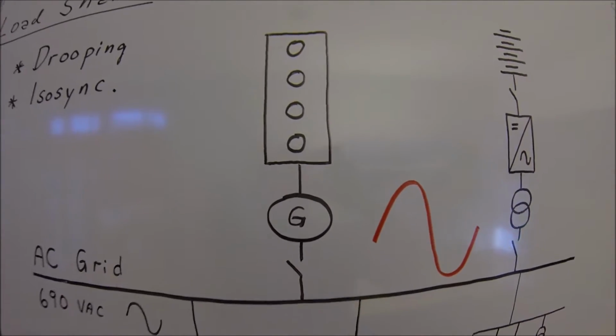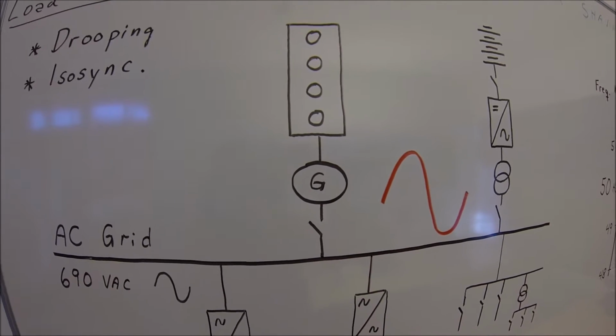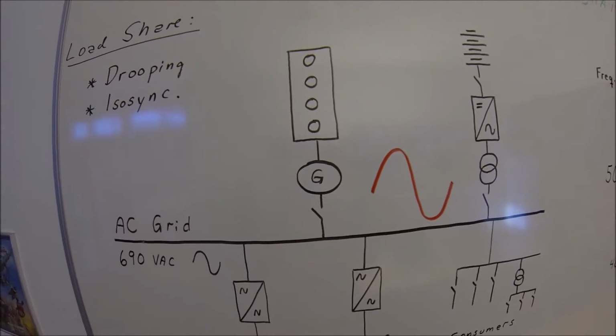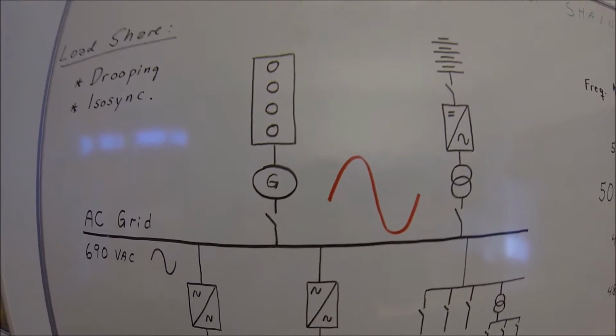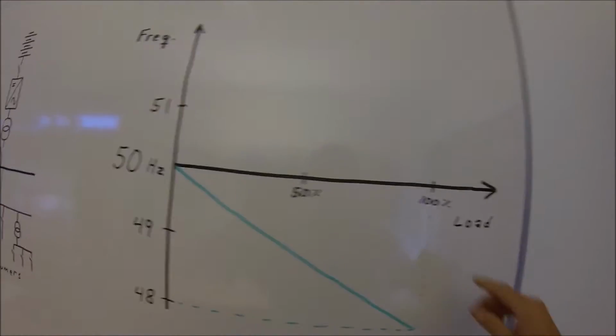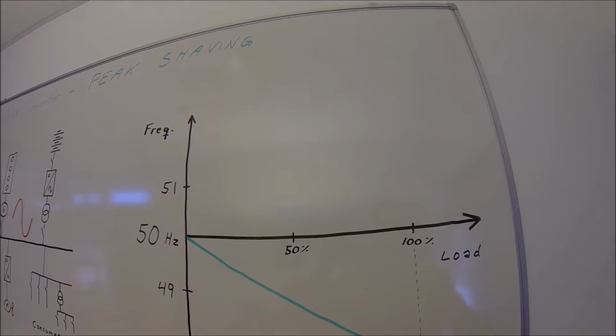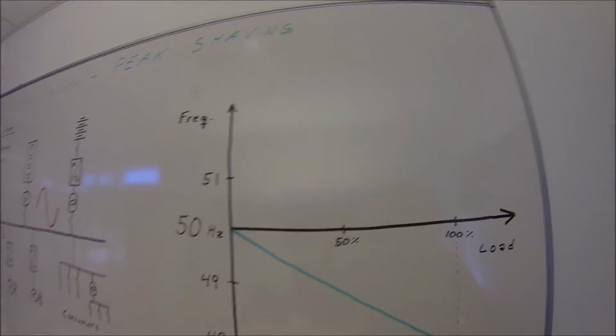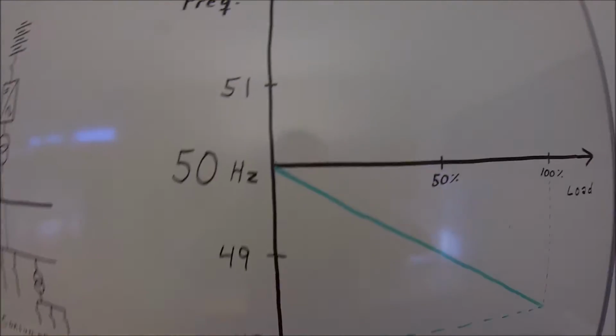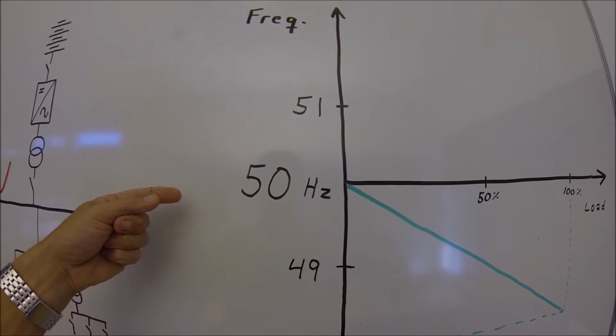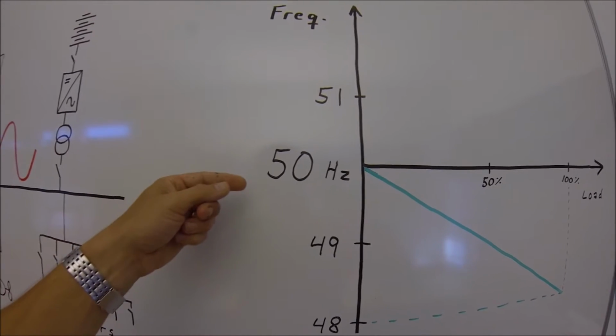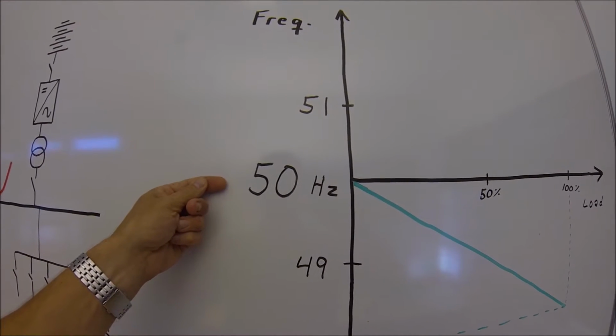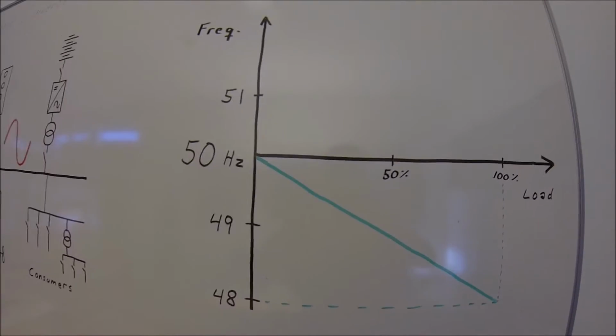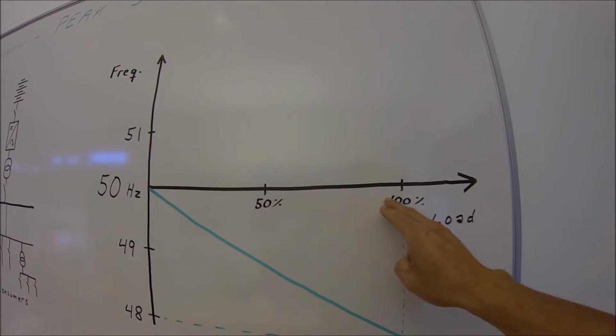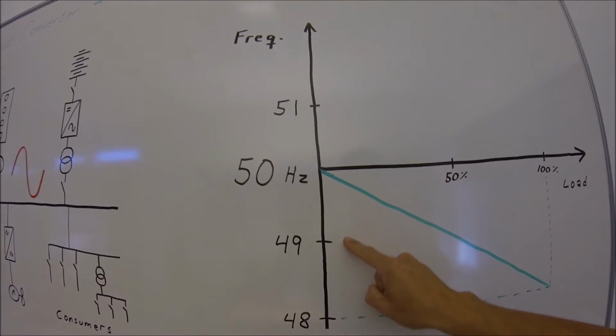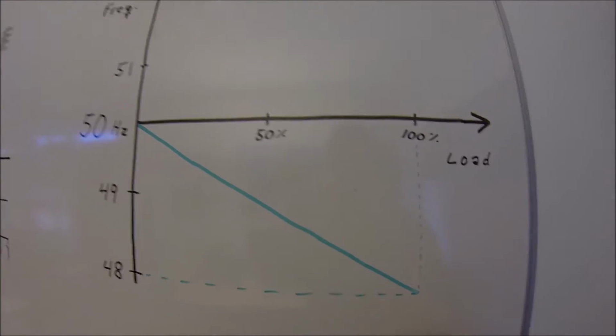Typically, all diesel engines have an inbuilt drooping function. What it does is droop off its frequency as a function of the load. It means you start with some base frequency. On a ship it could be 60 hertz, on shore it could be 50 hertz. Anyway, when the load increases, the frequency will drop off.